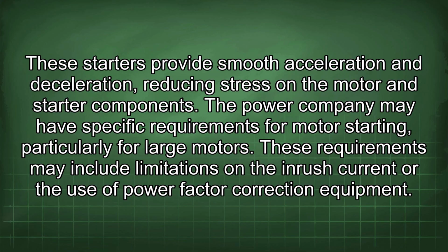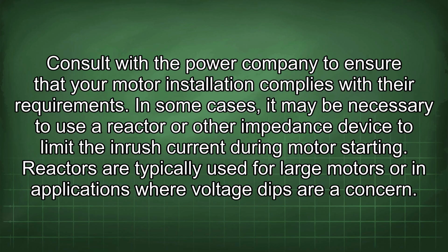The power company may have specific requirements for motor starting, particularly for large motors. These requirements may include limitations on the inrush current or the use of power factor correction equipment. Consult with the power company to ensure that your motor installation complies with their requirements.